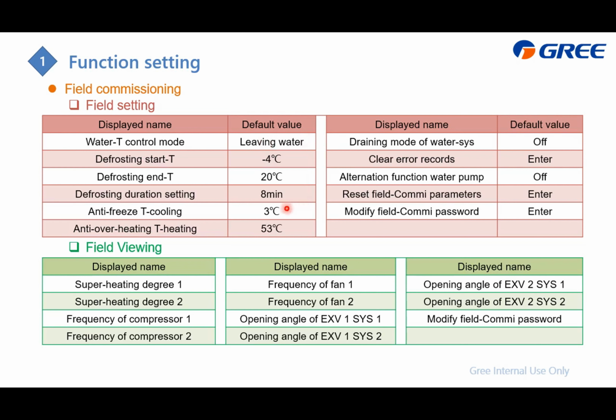And also the anti-freezing: when you apply the anti-freezer, you are allowed to change this value. Similar to the anti-overheating, when we detect the water is too hot, we will also trigger the error. And also set the alternate control for the water pump. And this one is for releasing all the water in the water system.